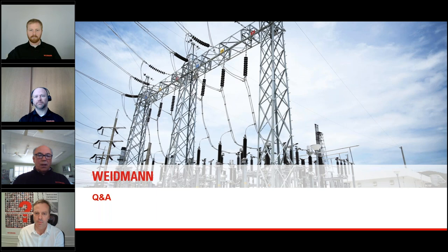And then I would recommend that you qualify the manufacturing plant, or if it's one of these multi-million dollar transformers, you actually do inspections of the unit as it's being manufactured. That would be the most reliable way to make sure that you're getting a high quality transformer. And if you don't have the expertise in house, use a consultant, someone that understands the manufacturing process and can go on site and view these critical manufacturing processes, one of which would be winding coils.